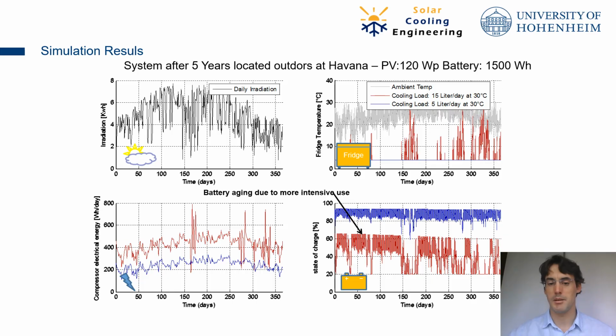The drinks are going to be warm, and the batteries will be destroyed after 5 years. You see the remaining capacity is only 65%, so you have to exchange the battery. So the user is not happy, and the batteries have to be replaced. This is due to a bad design of the system, because the system was designed for 5 liters per day and not for 15 liters per day.